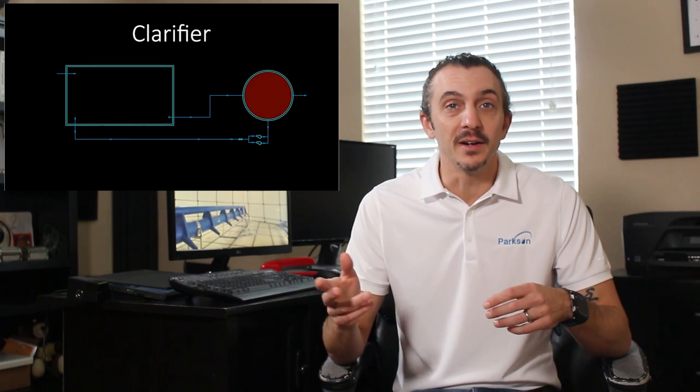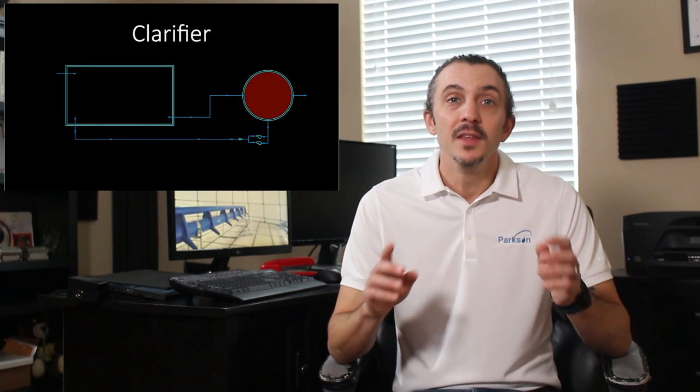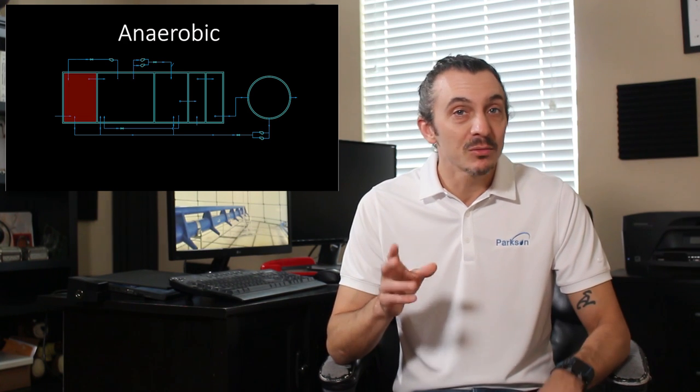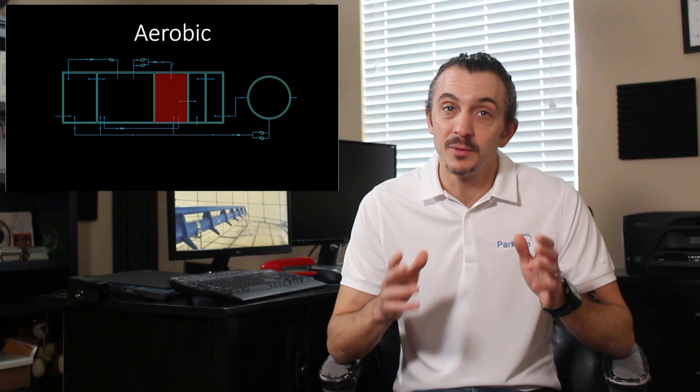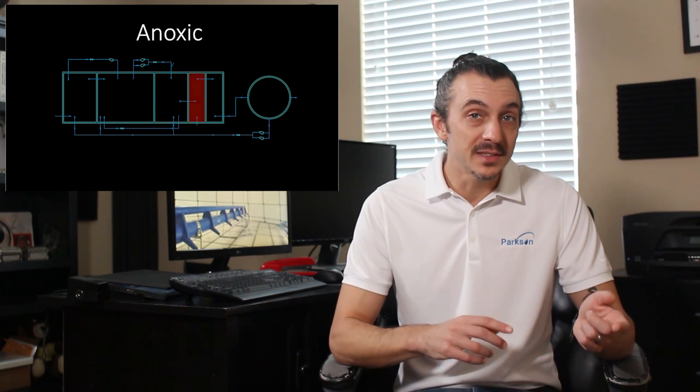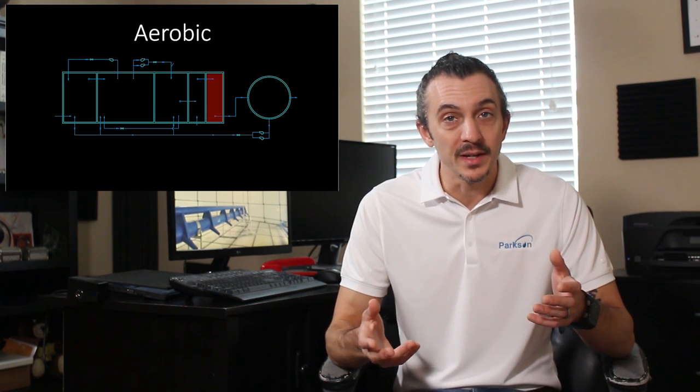Traditionally, each one of these steps is done in a separate tank. In its simplest form, this is a tank with oxygen, known as an aeration tank, followed by a clarifier, which is another tank. This can go all the way up to something like a five-stage Bardenpho system, with a tank with no oxygen known as an anaerobic tank, then a tank with only non-elemental oxygen known as an anoxic tank, then a tank with good old O2, an aerobic tank, another anoxic tank, and finally another aerobic tank — all followed by a clarifier. Yet another tank. That's a lot of tanks.